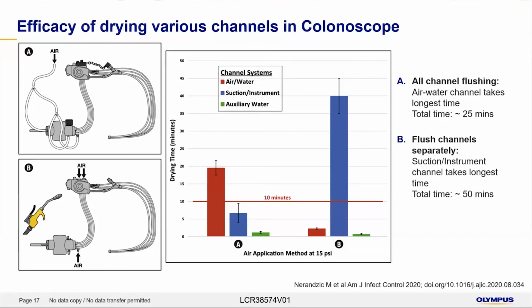Now, the data on the right, again, you can see if you use method A, which is the all-channel one, it takes at least 25 minutes to get all of the channels: the air water channel, the suction instrument, and the auxiliary water, red, blue, and green. And if you use method B, which is doing each channel independently and standing there for a period of time, it's going to take you a total of 50 minutes. And the channels that take the longest to dry differ depending on the method you use. The bottom line here is that you can't take a 1 or 5 minute air flush of these channels and think that you've actually got them adequately dry.